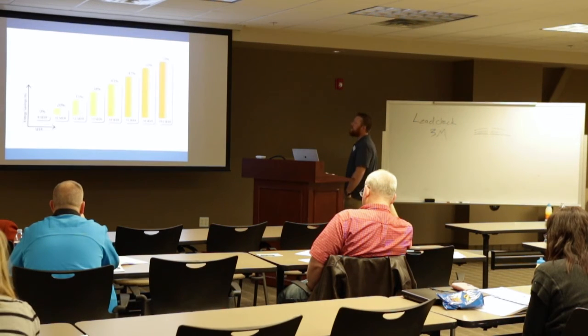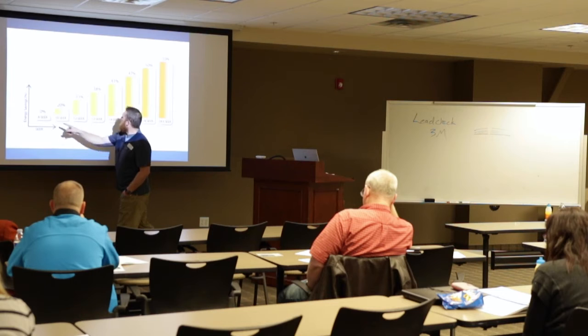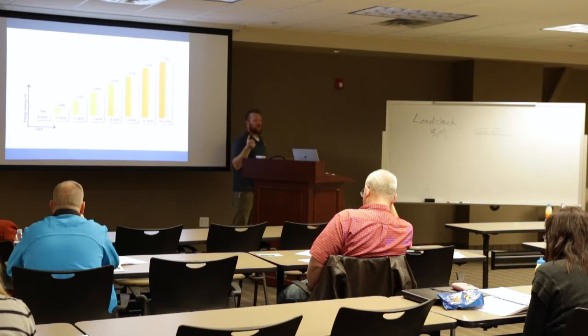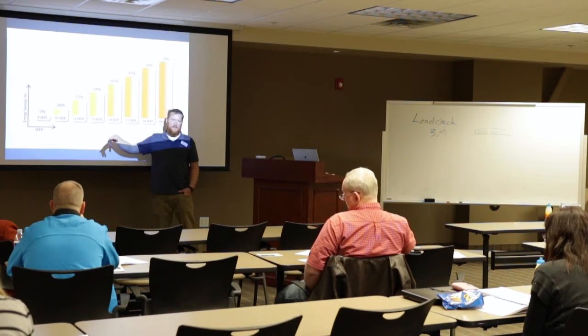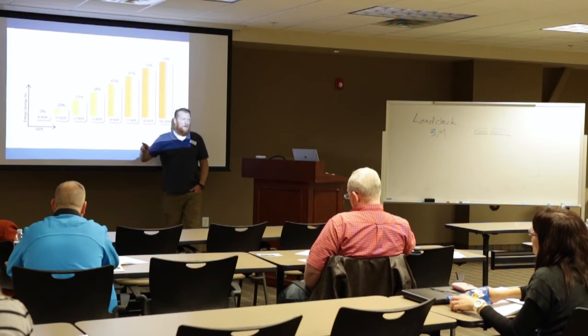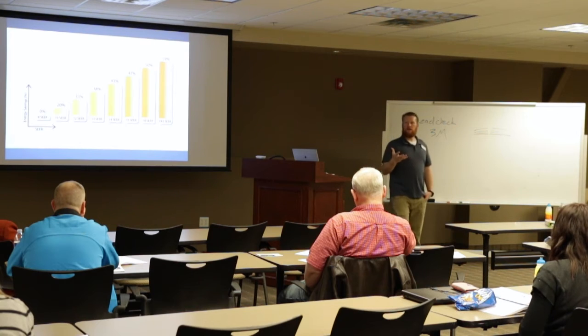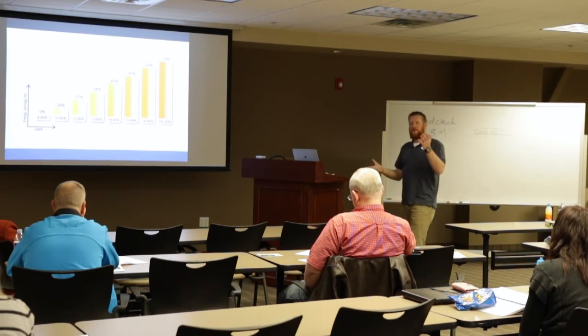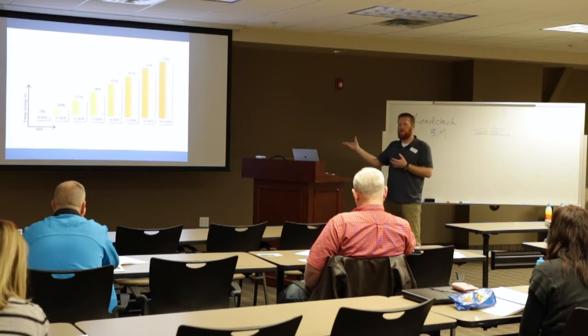What does that mean? This is your efficiency. So 8 SEER compared to a 19 and a half SEER, you're looking at almost 60% more efficient. If your air conditioner is more than 15 years old, it's probably in here. So this is a real easy calculation when clients are wondering, should we upgrade or not: what's your electric bill in the summer versus the winter? That difference is probably mostly your air conditioning bill.